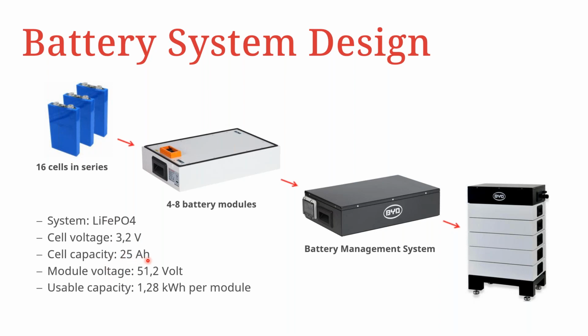If they were in parallel instead, the capacity and voltage relationship would be reversed, with voltage staying at 3.2. But since they're in series, the ampere hour rating remains the same at 25 ampere hours.